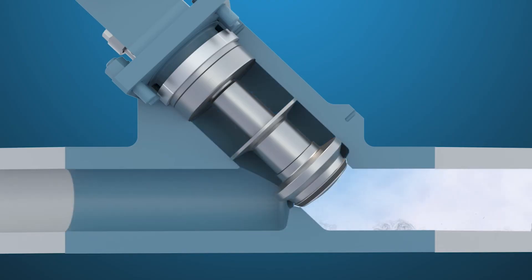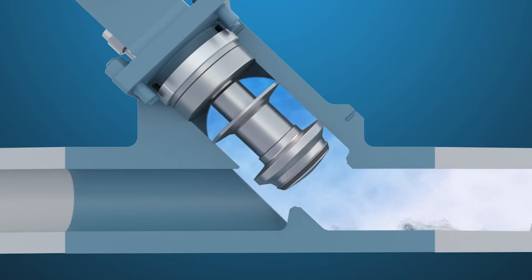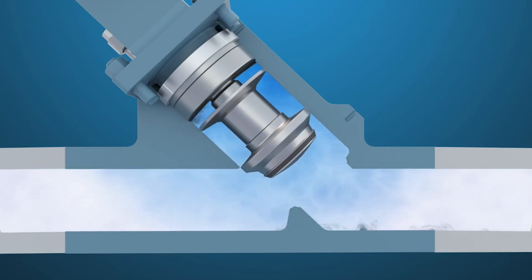A stop-check valve is required by boiler code when two or more boilers are connected to a common header for safety, but should not be relied upon as the primary shutoff valve.